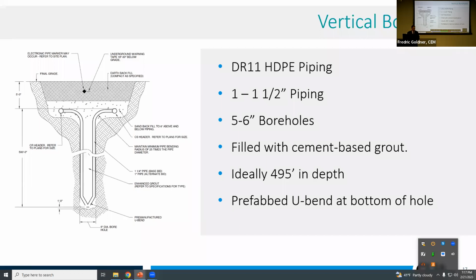Okay. So you go into, say, Florida. Florida is large limestone area. Yeah, it's got a 3-foot water table. Born and raised before there was a Florida man. Yeah, but that area, you could have your limestone foundation basically eaten out from under it. Oh yeah, and sinkholes. Yeah. Well, that's true. Typically in Florida, because of that water table, it's either an open loop standing column well, or they do that GeoDX, which has its own corrosion issues because they use copper pipe.